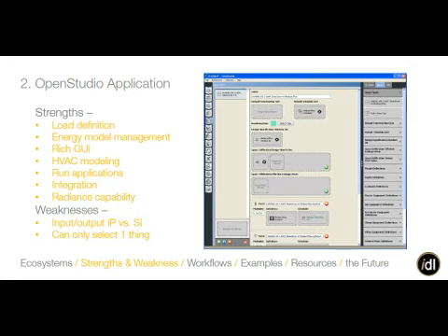So Dustin, if I did my load calc in this in OpenStudio, could you use this for your energy rebates? Would it be helpful? Yeah. So the rebates, a lot of times they require energy calculations for the custom incentives. And the way you do that is basically you have to convince the utility that this thing saves energy. They'll look at either a spreadsheet calculation or whatever justification you provide them. But if you point to an EnergyPlus model, they're much more apt to have a lot fewer questions about the energy savings because they know the underlying calculations were done right.